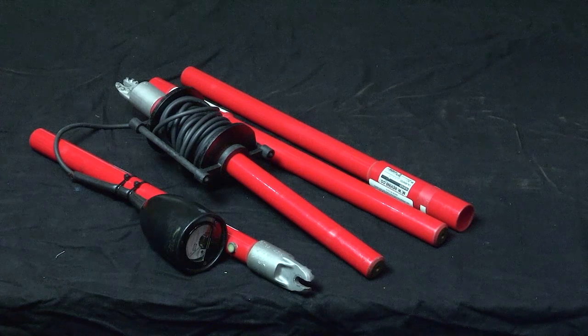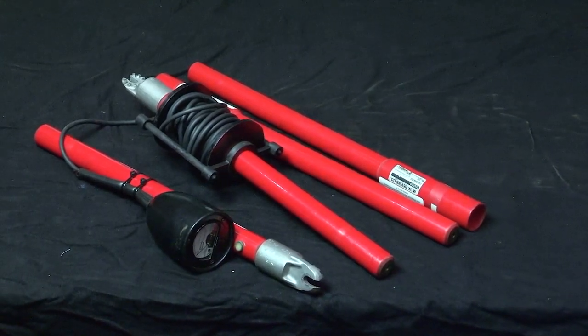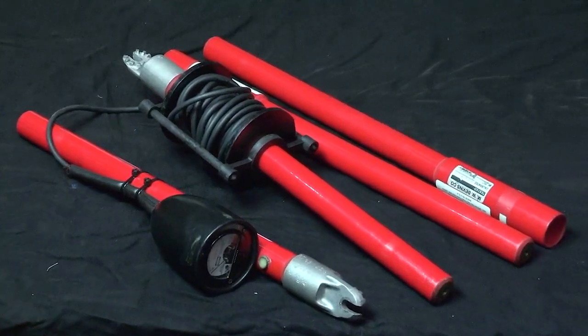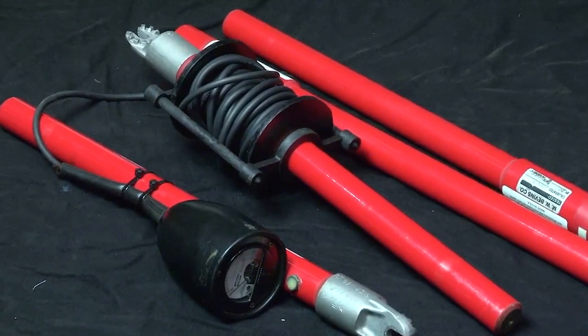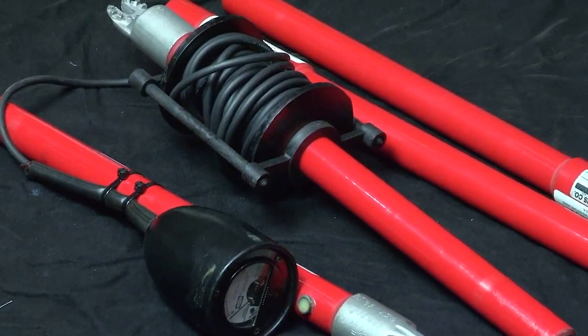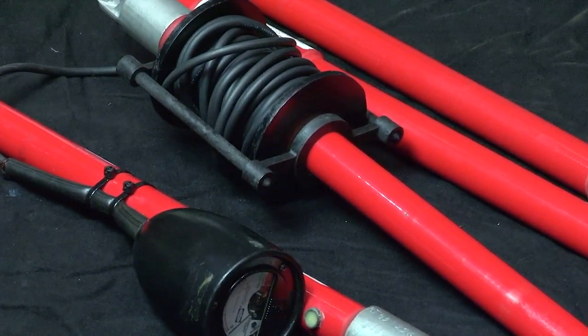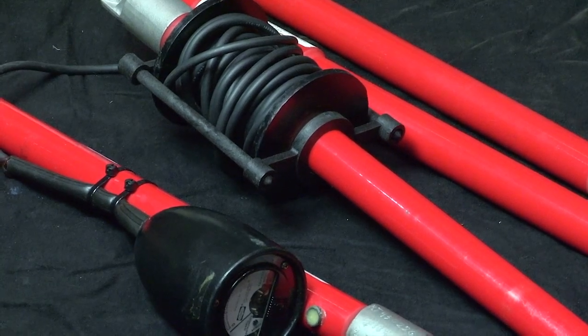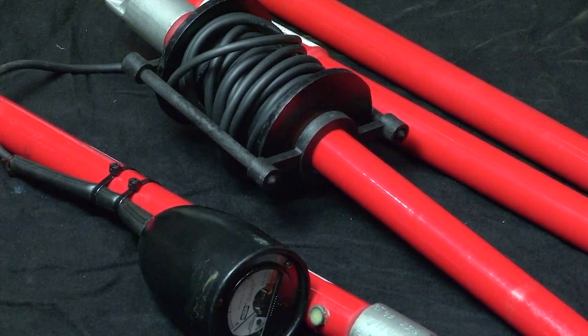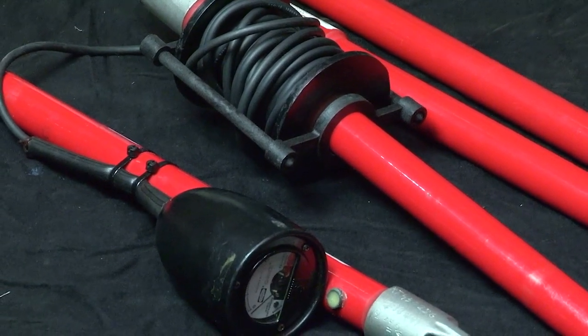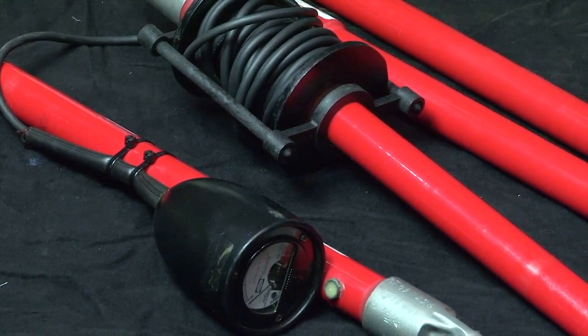Chance phasing sticks are the recommended tool for performing phase checks. Each testing unit consists of 2 insulated fiberglass sticks with end fittings threaded for interchangeable probes. The probe fittings couple with a high-impedance component encased in each stick. To complete the test circuit, a 22-foot length of insulated flexible cable is stored on the reel attached to one stick and connects to the voltmeter on the other stick. These phasing sticks can only be used on lines up to 36 kV. The cable insulation is limited to 15 kV for lightweight and ease of handling.